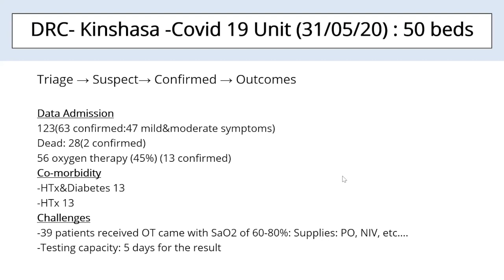But we have 2 sources of oxygen that we are using. One is oxygen cylinders, and we also have oxygen concentrators. The pulse oximeter, we use it in the unit to monitor the patients who are under oxygen, and at the same time to titrate the oxygen between the patients, and also to decide if a patient needs the oxygen cylinder or has to be put on the oxygen concentrator, because the oxygen concentrators can deliver only 5 to 10 liters of oxygen per minute, but for the oxygen cylinders, we can go up to 15 liters per minute.